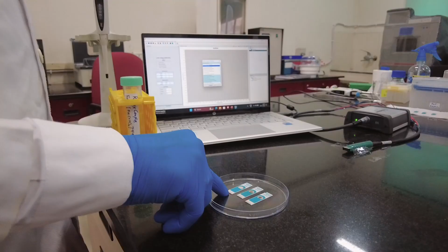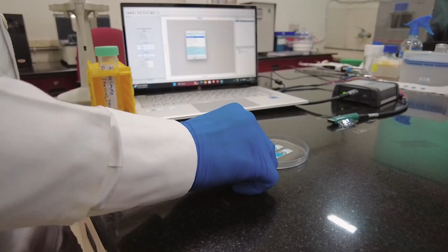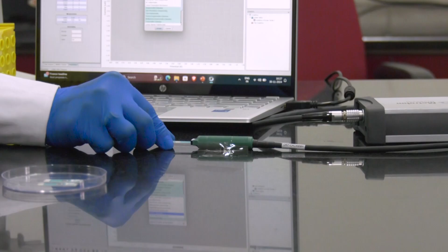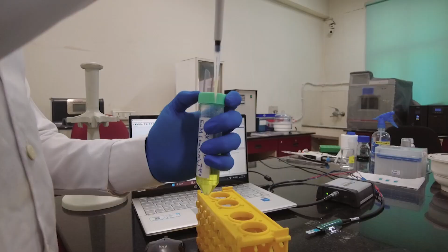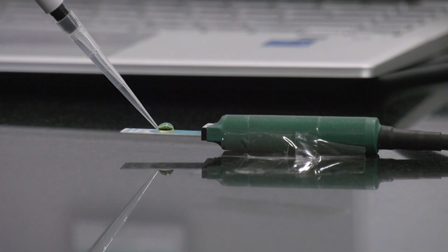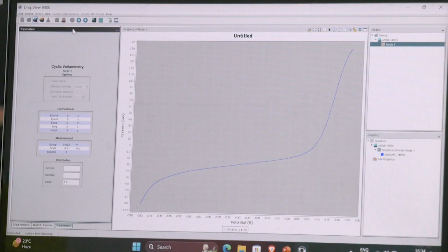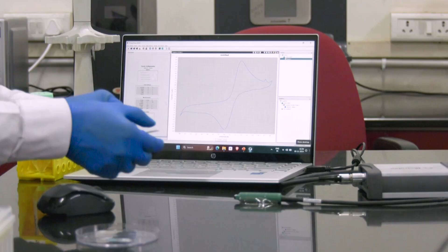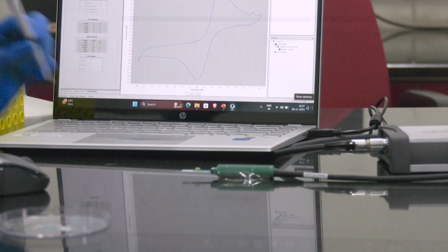Here we have the unmodified screen printed electrode, the screen printed electrode modified with amine graphene, and the modified screen printed electrode with antibody immobilized onto it. First, connect the unmodified electrode and add 50 microliters of redox solution to the working area. Run the CV. You can see the graph on the screen. Similarly, we will check the CV of the modified screen printed electrode. You can see that in the modified electrode there is an increase in the peak current.